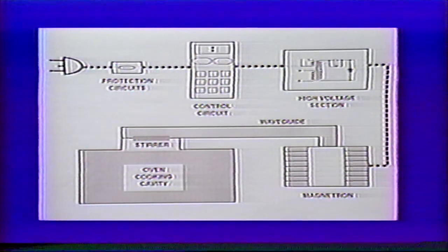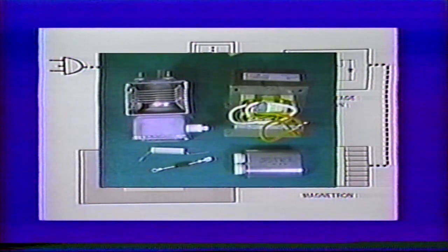Let's now move on to the high voltage section. This section includes the high voltage transformer, which steps up the input 120 volts to approximately 2,500 volts AC. This voltage is then applied to the voltage doubling circuit, which includes the high voltage oil-filled capacitor. The capacitor will charge to approximately 4,000 peak volts. Attached to the capacitor, you'll find a diode or a rectifier, which changes alternating AC current to pulsating direct current.